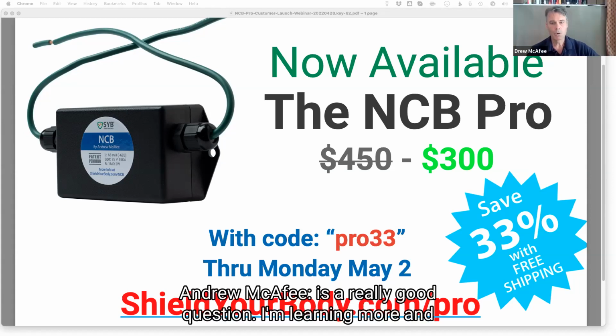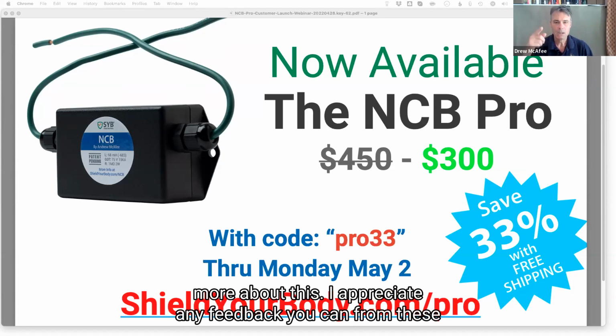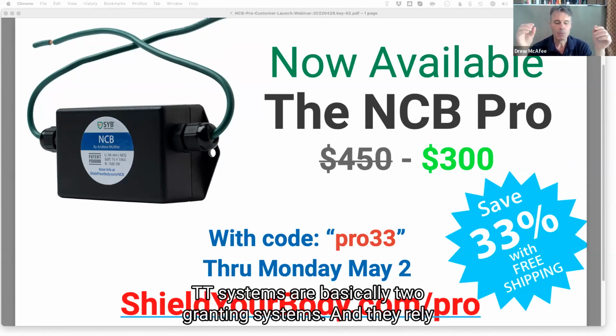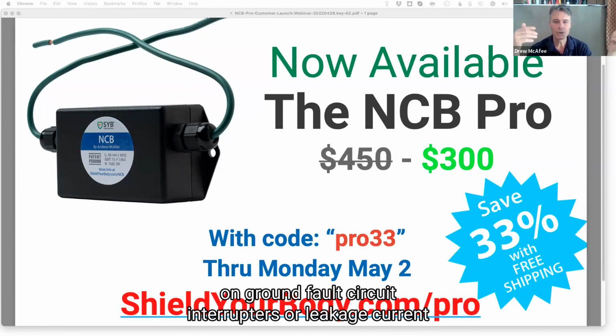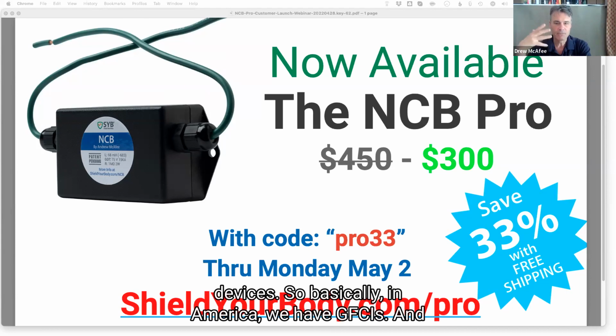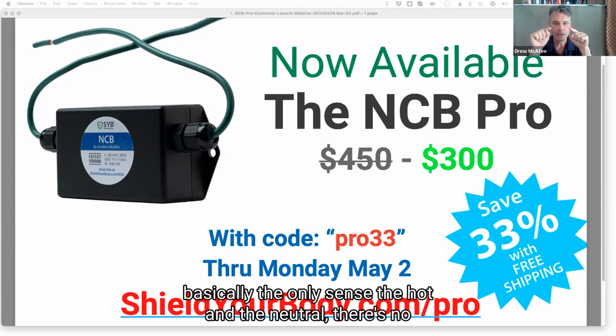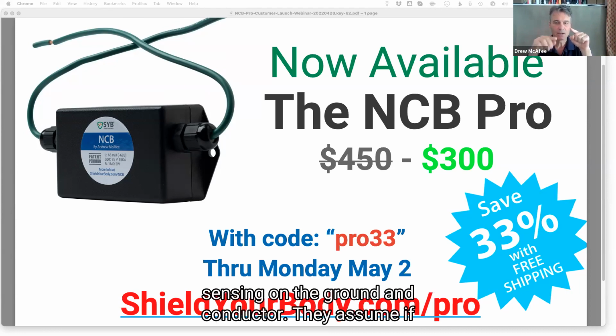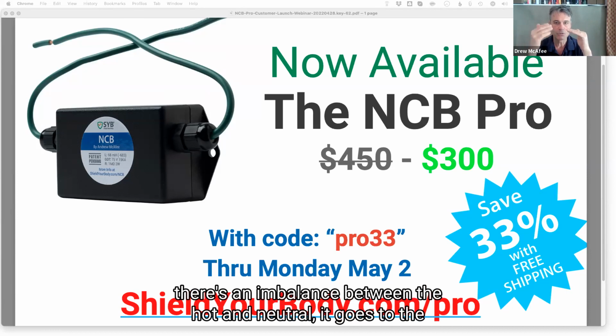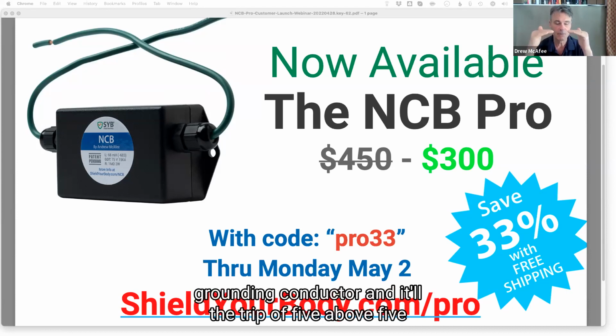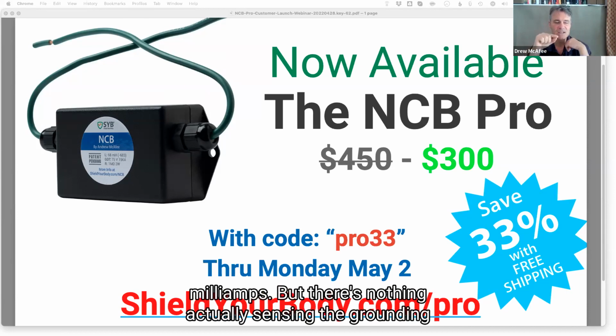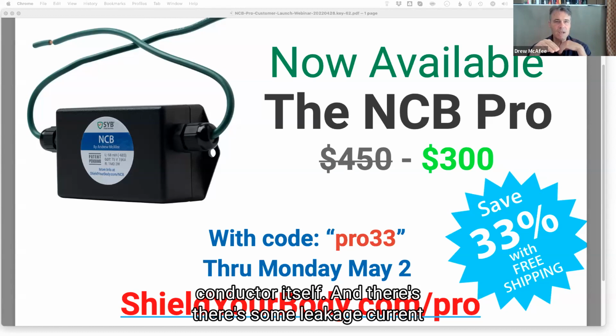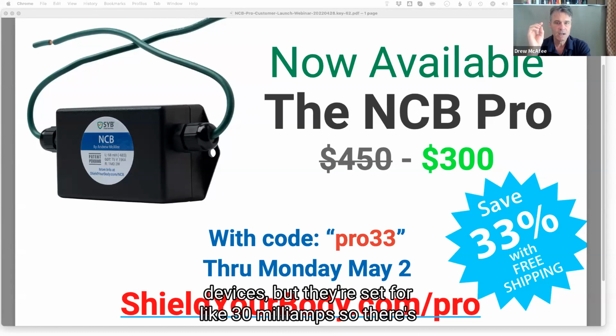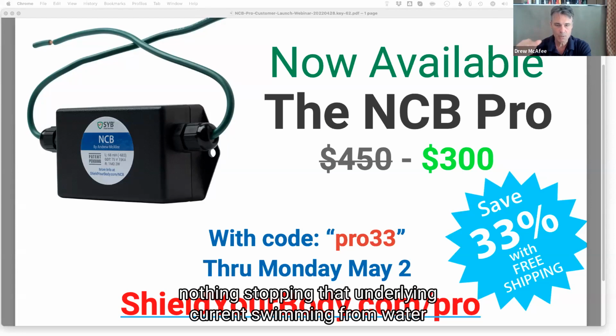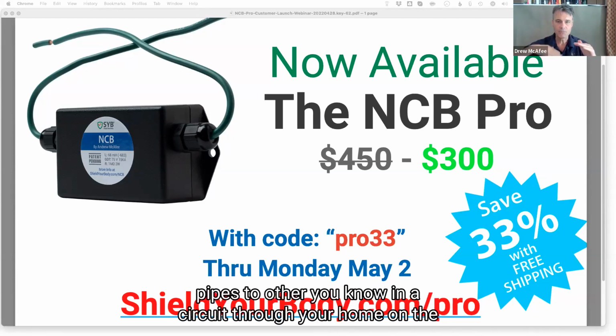That's a really good question, I'm learning more and more about this, and I appreciate any feedback on these TT systems - basically two grounding systems that rely on ground fault circuit interrupters or leakage current devices. In America we have GFCIs, which only sense the hot and the neutral - there's no sensing on the grounding conductor itself. They assume if there's an imbalance between hot and neutral it goes to the grounding conductor, and they'll trip above 5 milliamps. But nothing actually senses the grounding conductor. Some leakage current devices are set for around 30 milliamps, so there's nothing stopping that underlying current from traveling through water pipes and other paths in a circuit through your home on the grounding system.